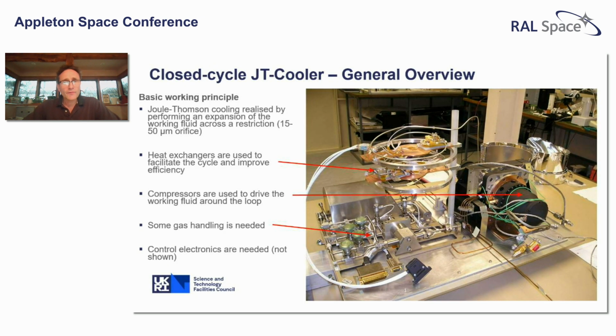This is a general overview of the cooler. I've got a picture there. It's obviously quite difficult to make a lot of things out. The basic principle of a JT cooler is to perform an expansion of the working fluid across a restriction, and you get Joule-Thomson cooling in that way. The heat exchangers of the cooler are there to facilitate the thermodynamic cycle and to improve the efficiency. The compressors are the workhorse. They drive the fluid around the loop. And some gas handling is needed as well. So I will go through all of these in the next few slides very quickly. Control electronics are also needed. They're not shown in this picture. This is actually a picture of the Planck cooler while we were assembling it for unit level tests.